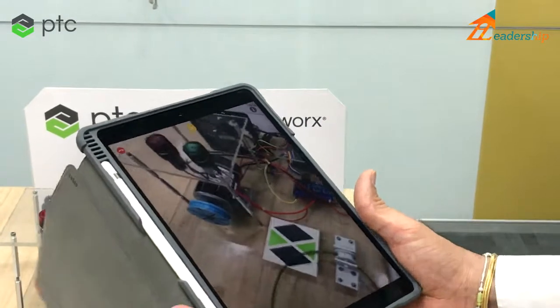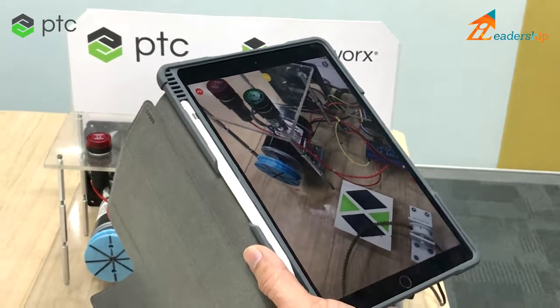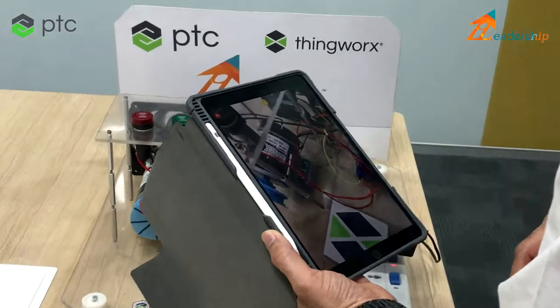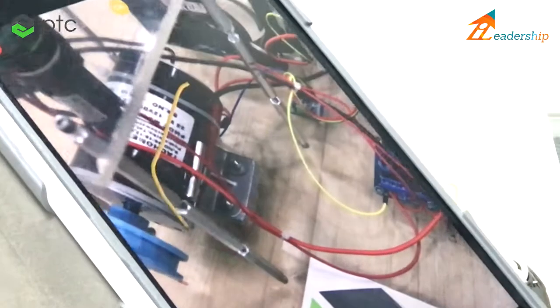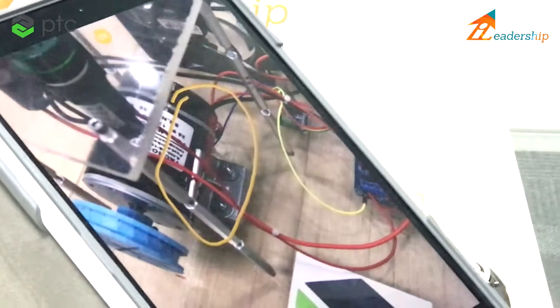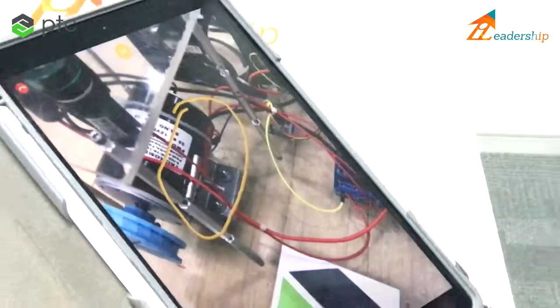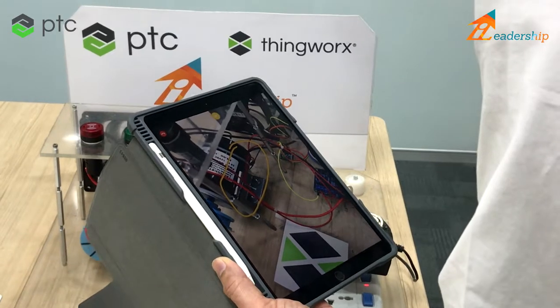Okay, sure. Just focus on, now I can see the motor actually. Just go a little bit down that panel there. Yeah, exactly. Just hold on for a second. You see here, this particular thing? What I've highlighted in yellow? Yes. That's the thermal sensor which measures the temperature. So probably you need to relook at that. At the same time, I also want you to check maybe the vibration and also the current. The vibration sensor is slightly behind the cooling unit.